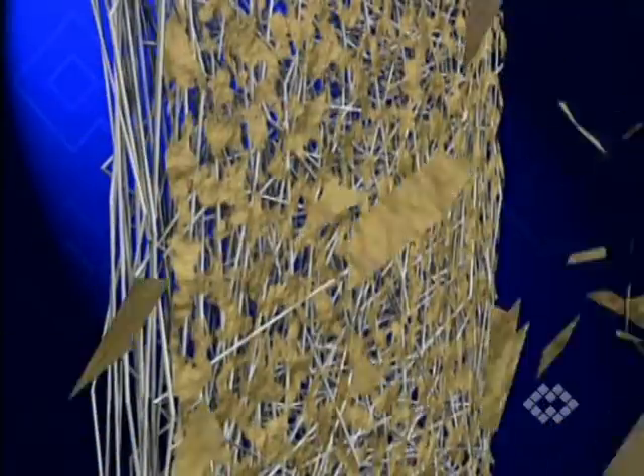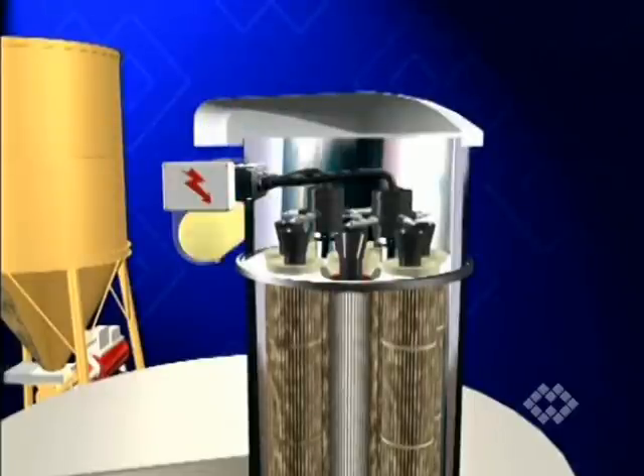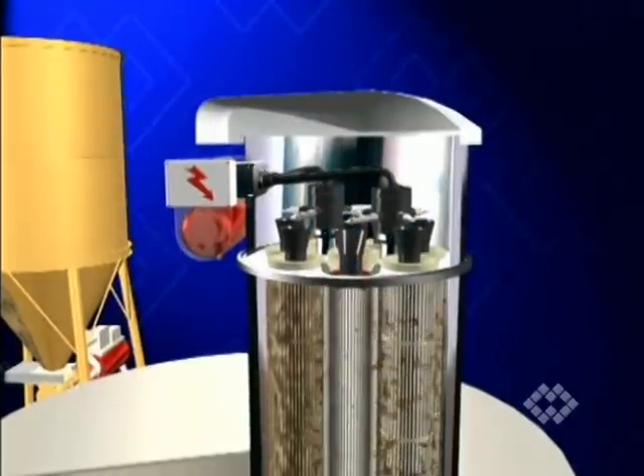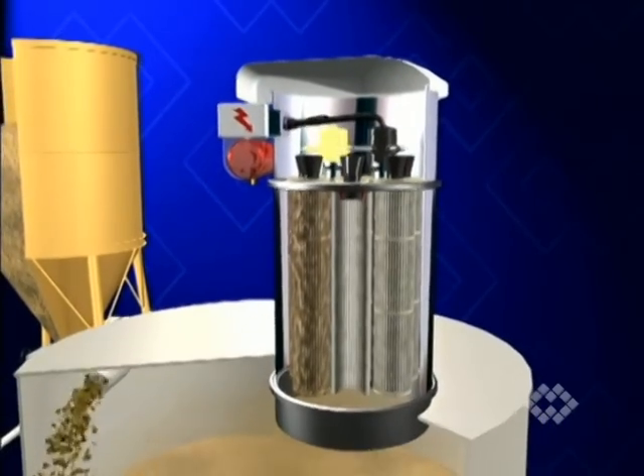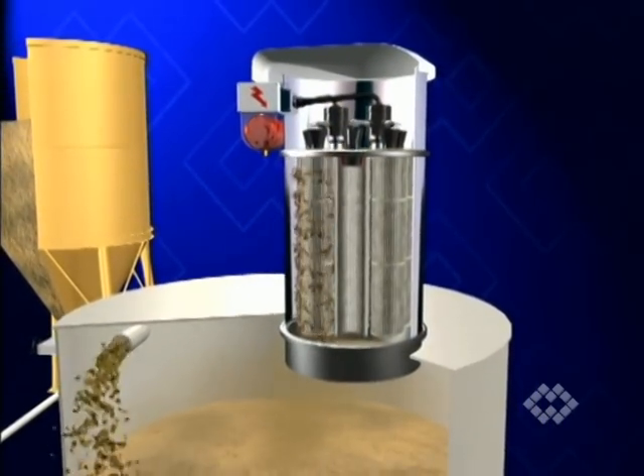This so-called reverse air jet passes from inside the cartridges through the media, removing the layer of dust deposit on the outside of the cartridge elements. The dust particles fall back down into the hopper.